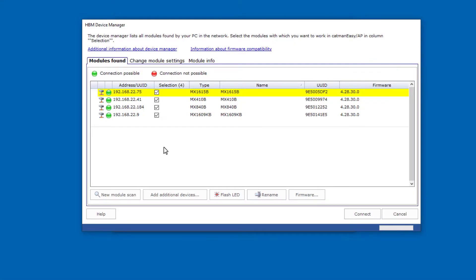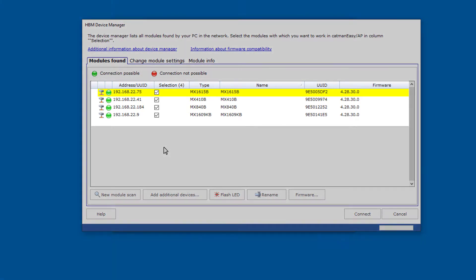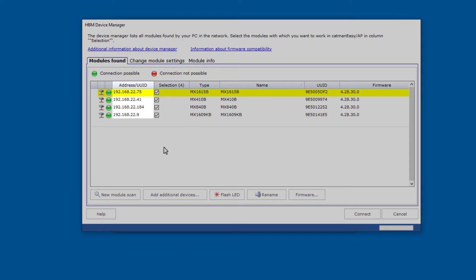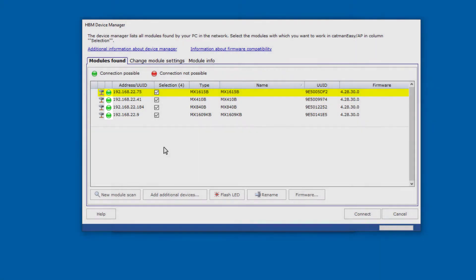The HBM device manager now displays all the modules found. If the modules are connected via Ethernet, you can see the Ethernet addresses of the modules here. If the green symbols are visible on all modules, you can connect to the modules and measure. Here's a hint: the modules are set to DHCP at the factory. This means that addresses are automatically assigned to the modules.